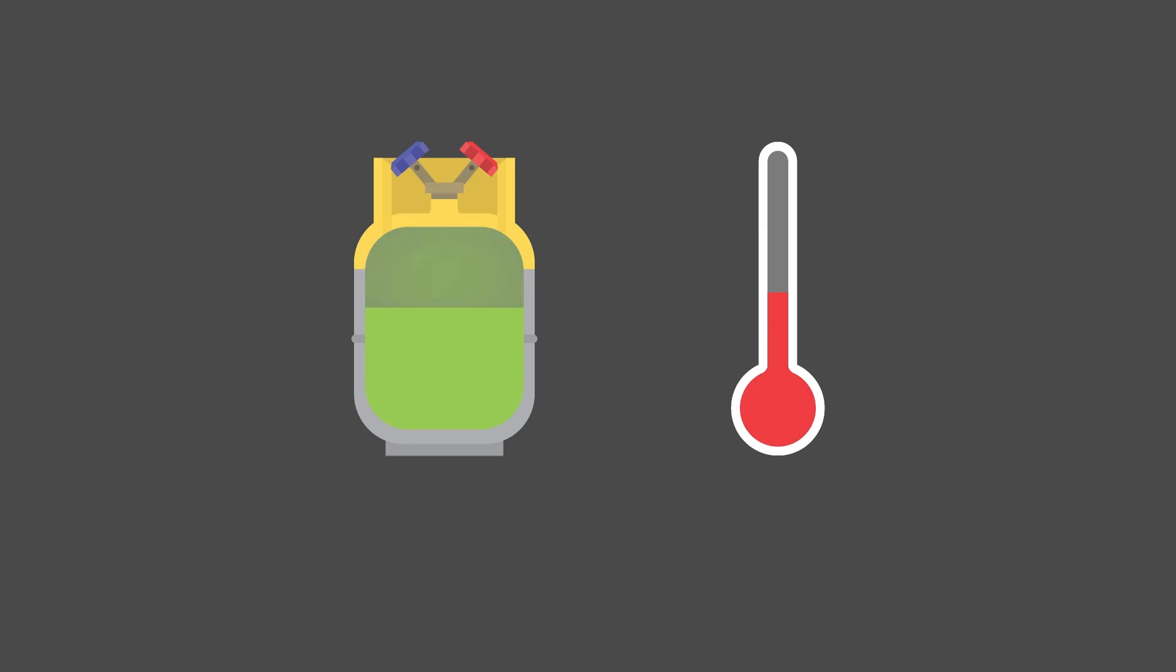Since refrigerant expands as temperature increases, it's extremely important never to overfill the cylinder. When a cylinder is overfilled with liquid refrigerant, a slight rise in temperature can lead to an explosion.